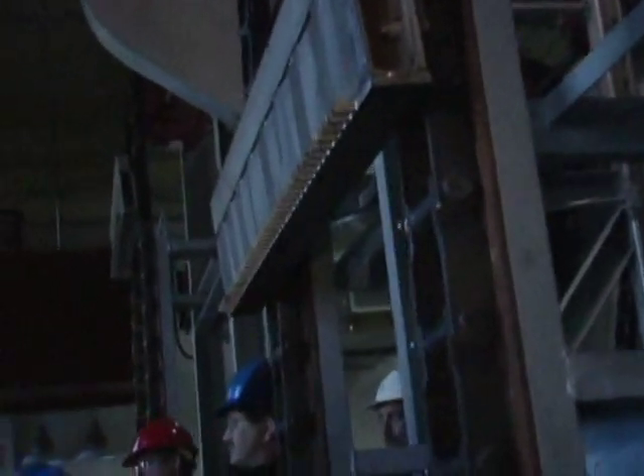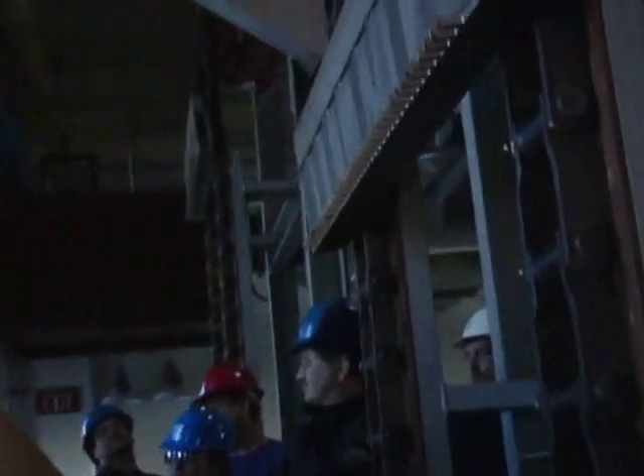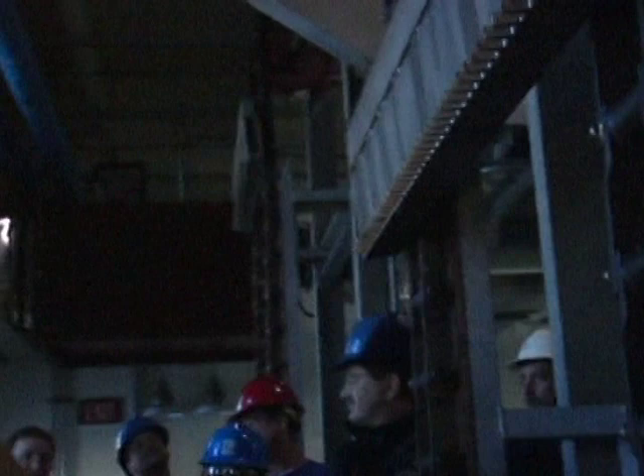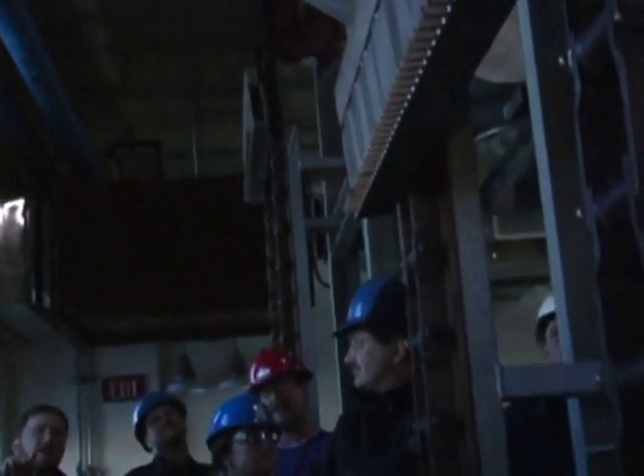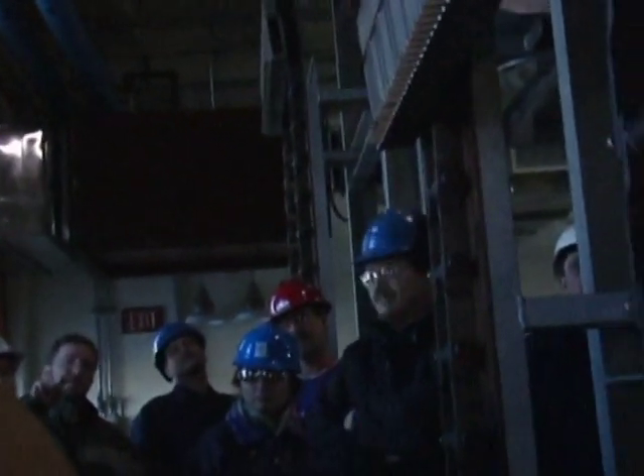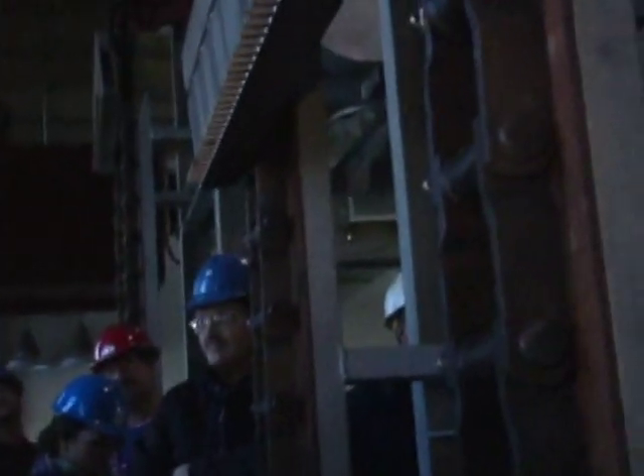I have a question. Yes. When we come in here and inspect the equipment, we put it in hand and make sure it's operating correctly. We go to put that back in auto. We have to go back to SCADA and also put it back in auto. In other words, like at the primaries, if we manually run the scum cross, you have to go back to SCADA and put it back in automatic to run its cycle.